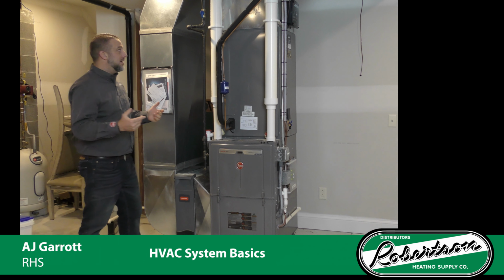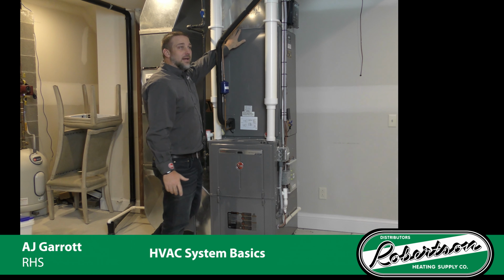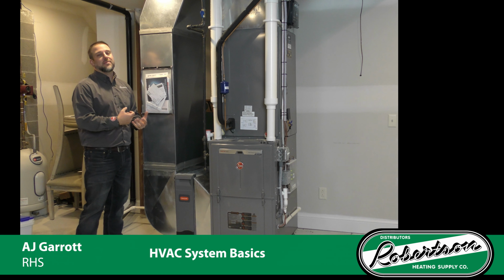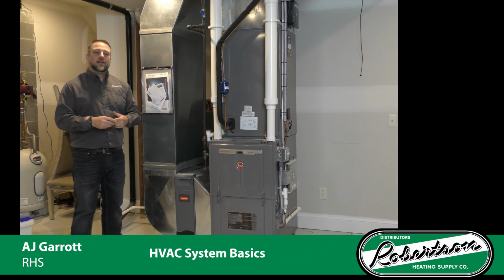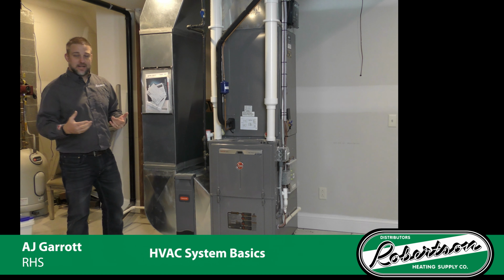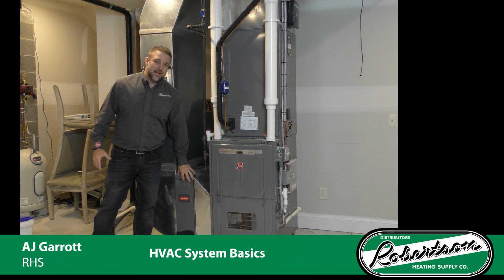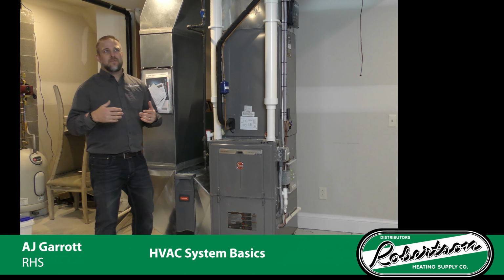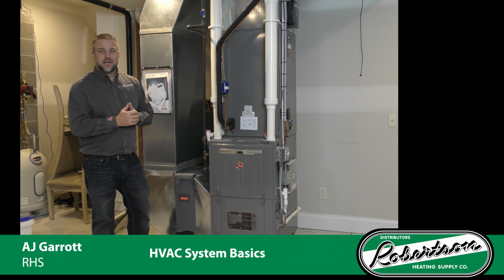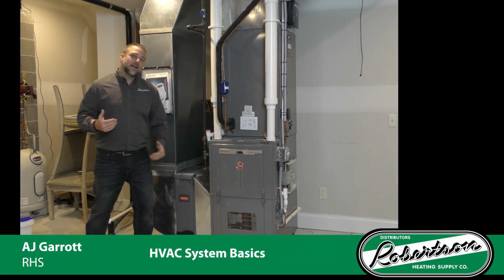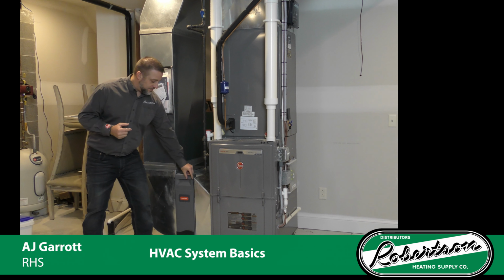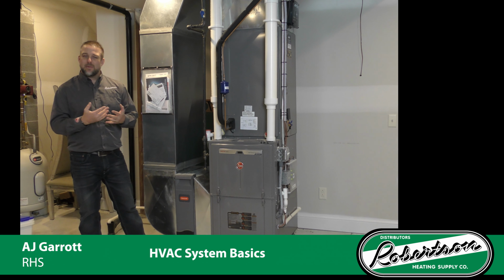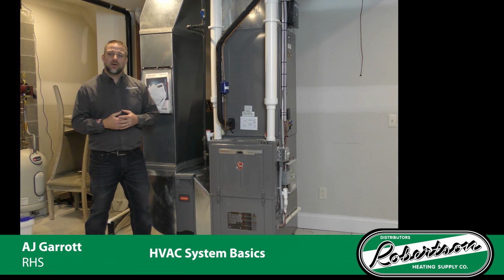On the same side, in the return plenum, it's right here is called a filter. The filter traps any kind of particles coming through the air, like dust and spores and things like that. This here is actually a media filter. It's about 4 inches wide, and filters comes in very many different shapes and sizes. The basic filters that we find in an HVAC system are 1 inch wide, and they could be media filters as well, or they could be just a normal fiberglass or horsehair kind of filter.